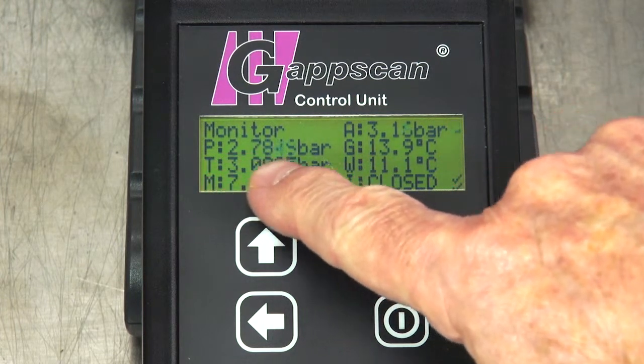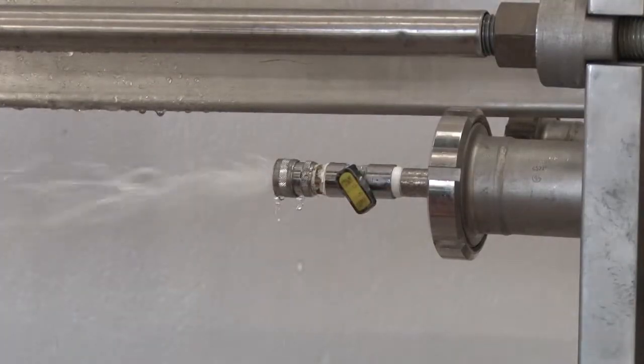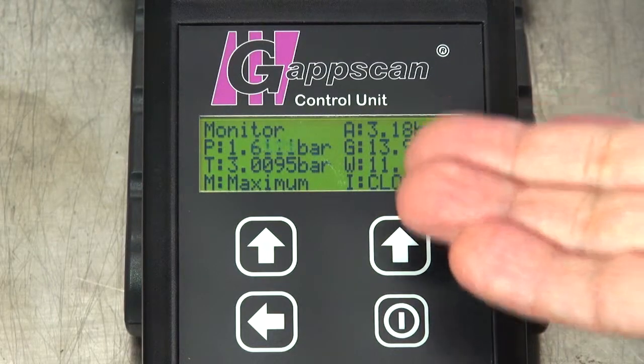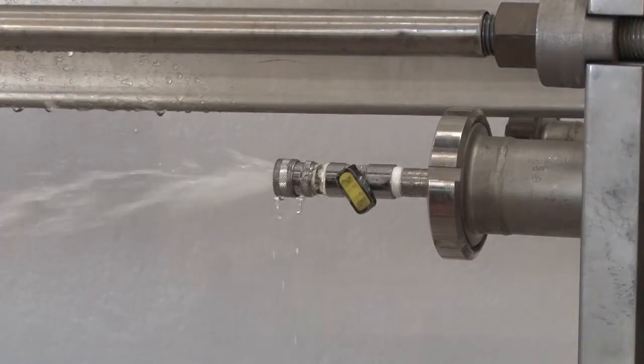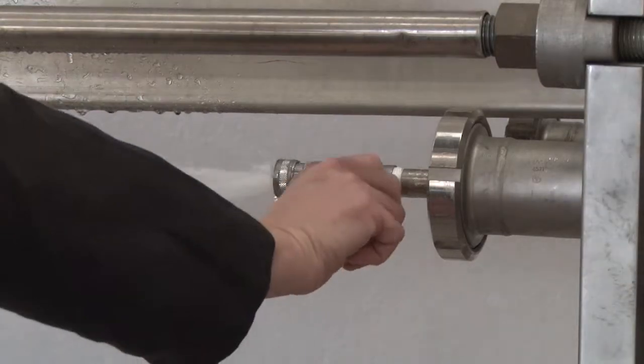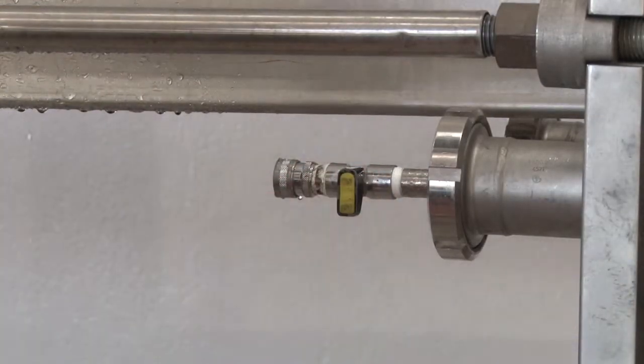If the live pressure P does not stabilise within 2 decimal places of the target pressure T, as shown here, then it usually means you have air in the system. Open the outlet valve on the exchanger to bleed water through. The pressure drops. Close the valve and the pressure builds again and should stabilise.